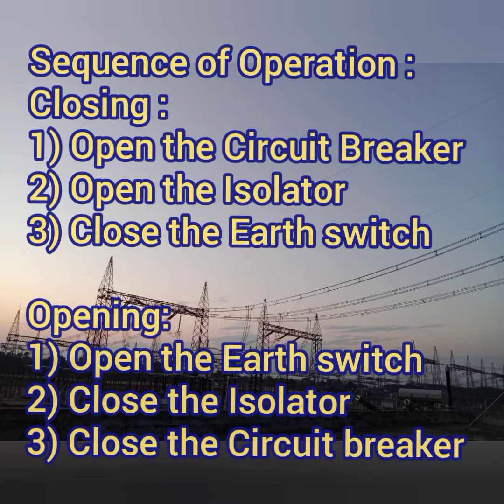Coming to the operation sequence of the earth switch, normally in substation we need to carry out the following sequence for opening and closing. For closing the earth switch, first we need to open the circuit breaker, then we need to open the isolator, and at last we need to close the earth switch.